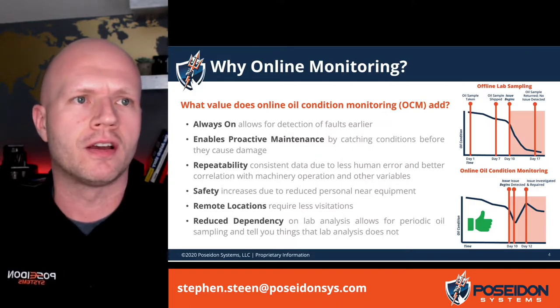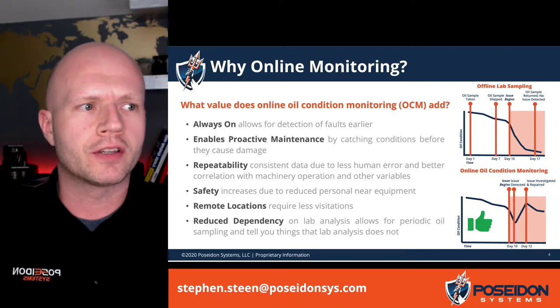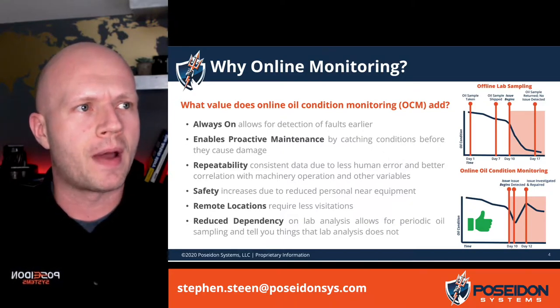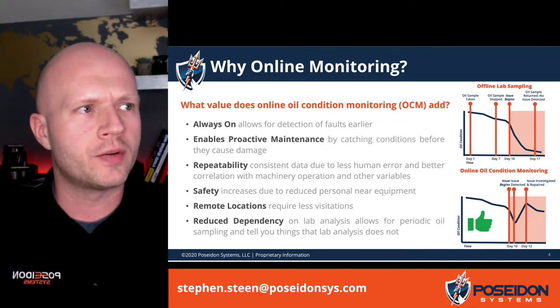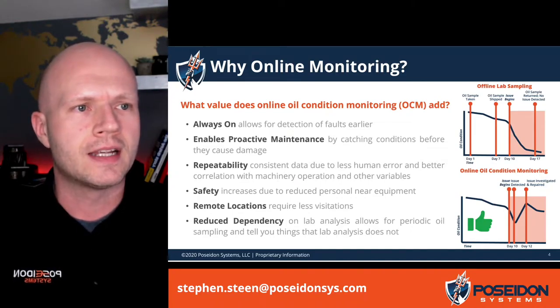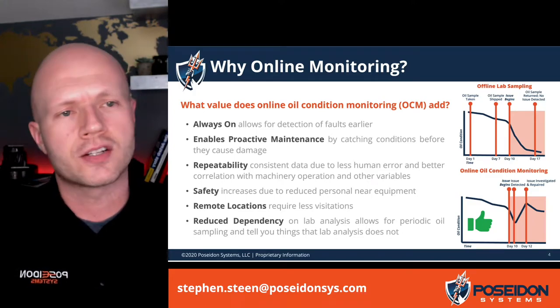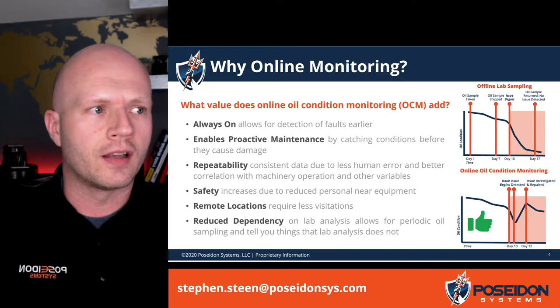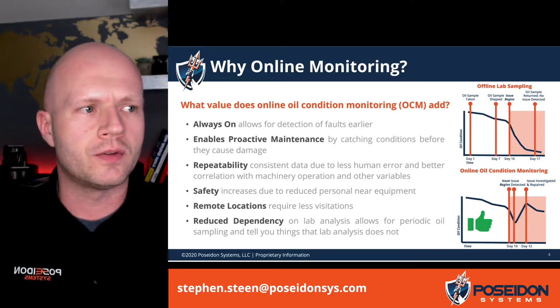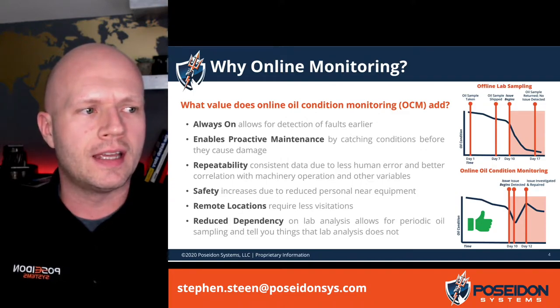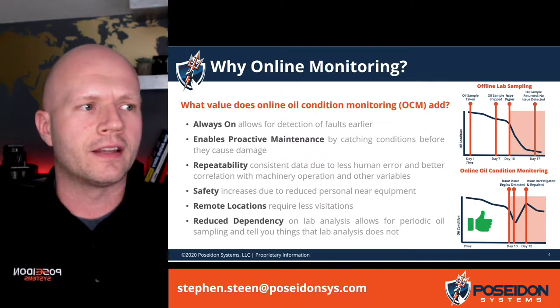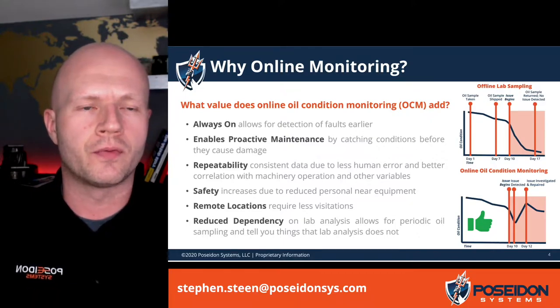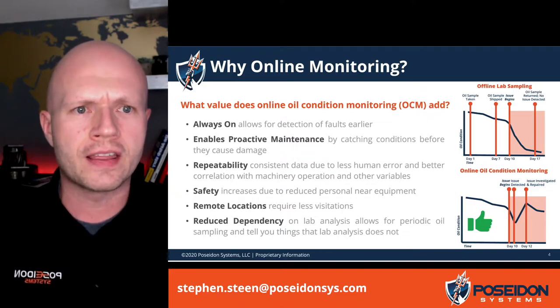Let's talk about the value of online oil condition monitoring. If you look at the graphs on the right hand side, you can see an example of offline oil analysis — a theoretical example of when something might go bad versus when you take a sample. At some point an issue begins, and you may or may not have a good sampling timeframe set up to catch it. In some cases you may actually have a fault starting to occur and get a result back from the oil sample that there's no problem. One of the key values with online oil condition monitoring is that it is always on. When the issue starts to begin and we're measuring those indications of a problem, detection can come much earlier. The issue can be investigated and repaired. It really does enable proactive maintenance by catching those conditions before a lot of the damage would occur.